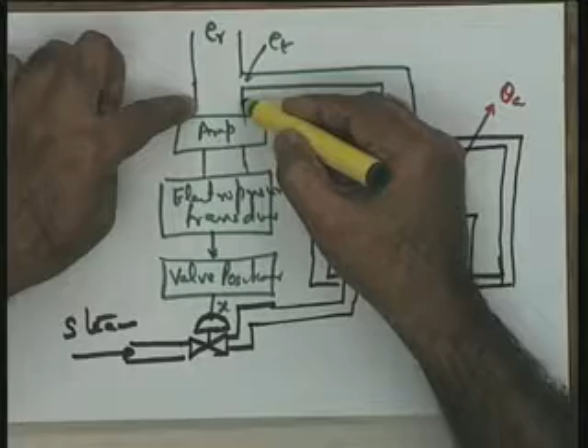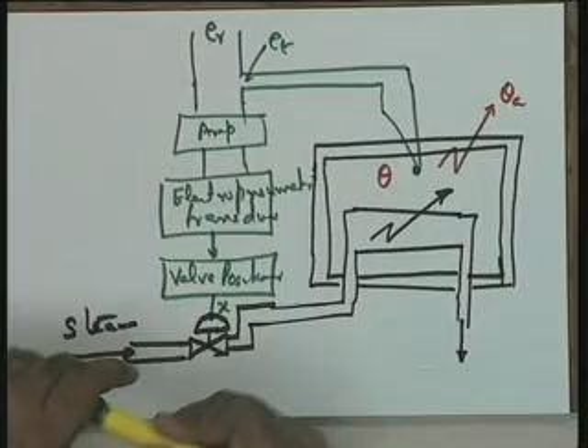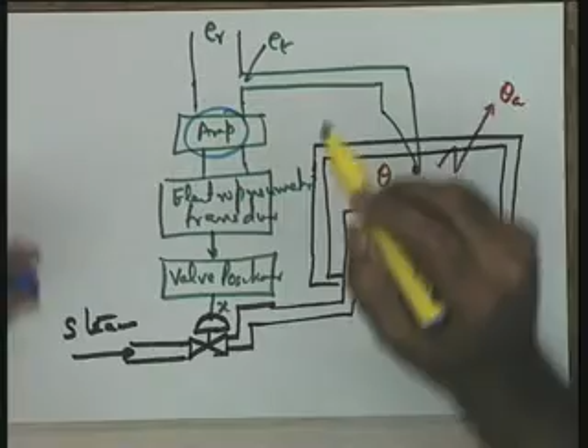The theta r, E_R proportional to theta r, the thermocouple, here the voltage, error voltage, the amplifier voltage is going to the electro-pneumatic transducer to the valve positioner, positioning the valve to regulate the steam and hence to regulate the temperature theta. Now I want to see the effect of only proportional control, that is, I want only an amplifier here which can control the variable Kc. I want to see how the proportional control is going to affect the various performance specifications I have already given to you. Okay? You will help me now, please.